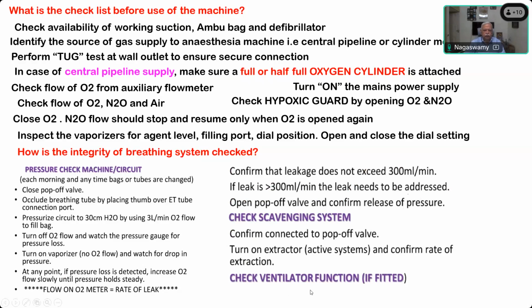And similarly, check ventilator function if it is also fitted. Make sure that it is. For checking the ventilator only, you need a test lung where you can attach it to the endotracheal tube connector end, and you can operate the ventilator to see whether the bag is expanding and collapsing correctly. Okay, so this is how the breathing system integrity is checked.